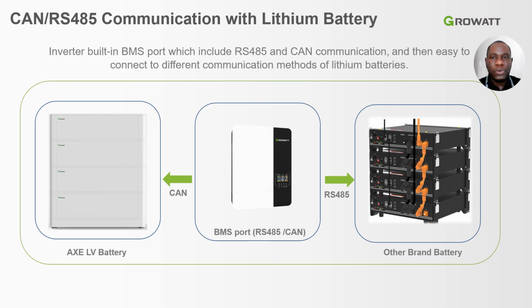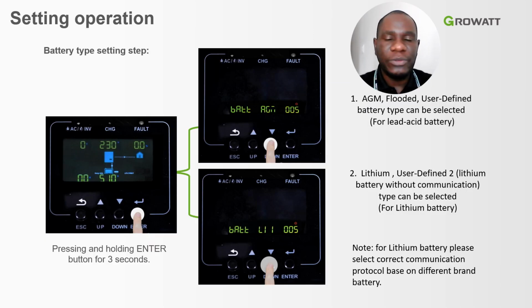Then, in terms of BMS, which is the communication between the battery management system and the inverter, we have an inverter built-in BMS port, which includes the RS485 and the CAN port. For other battery brands, you use the RS485, but with the AXE low voltage batteries, you use the CAN port, as you can see in the pictures. Then for the setting operation, you need to tell your inverter that it is operating with either an AGM battery or a lithium battery. This is program number 5. As I mentioned before, long press your enter button for at least 3 seconds. Then it will help you to select the program, which is program number 5. From program number 5, you move on to select what type of battery is connected to this inverter using your up and down arrow buttons.